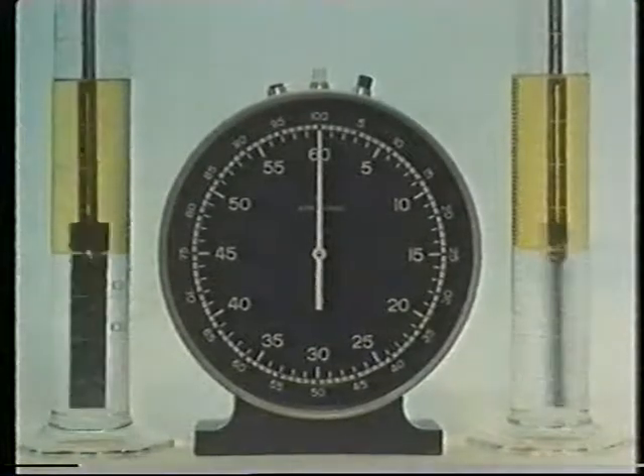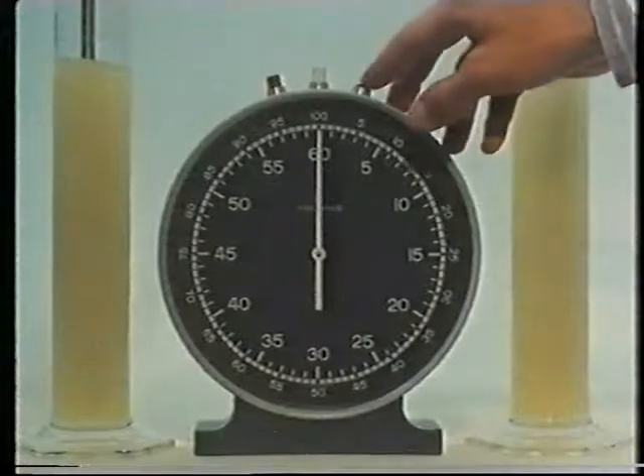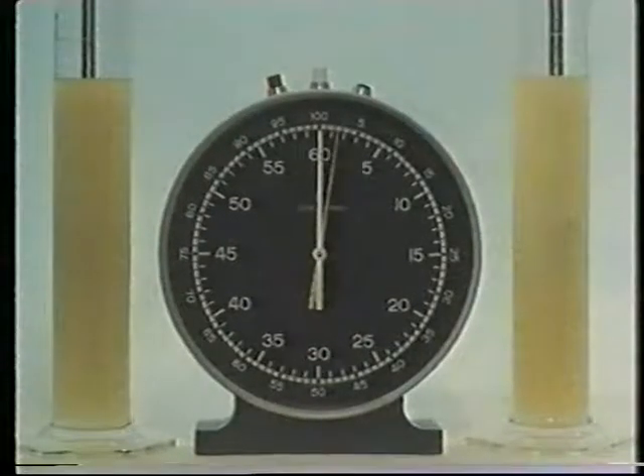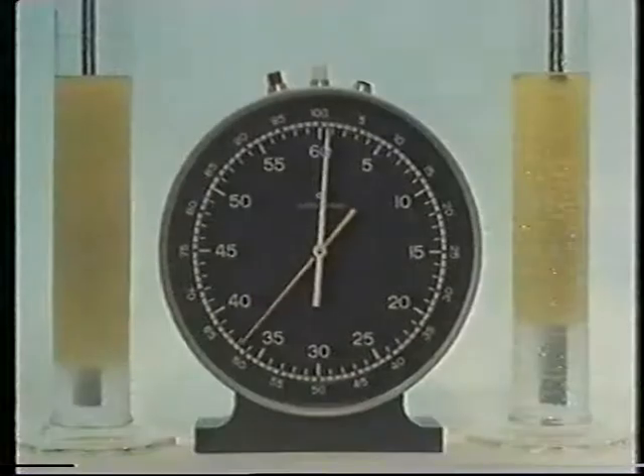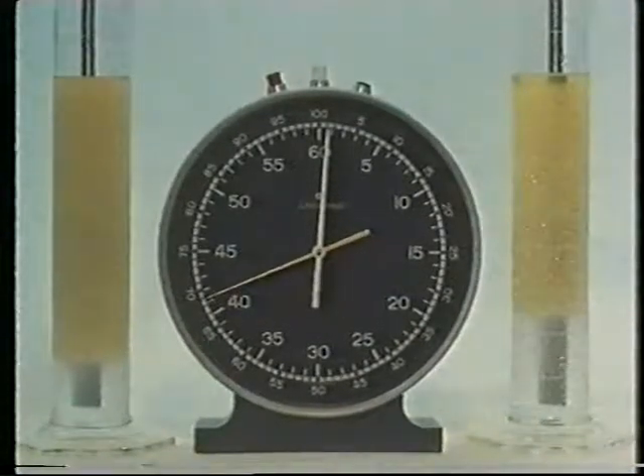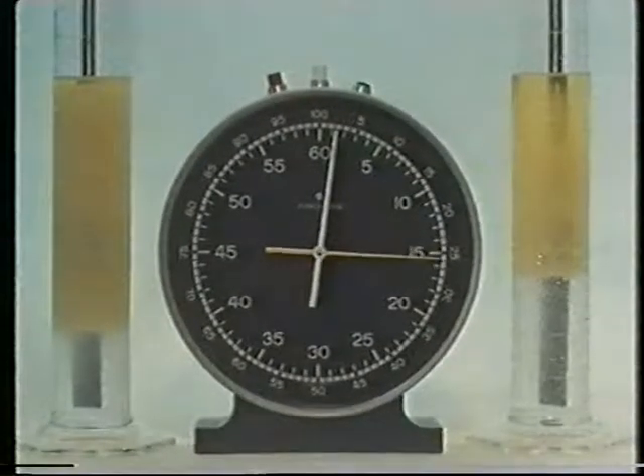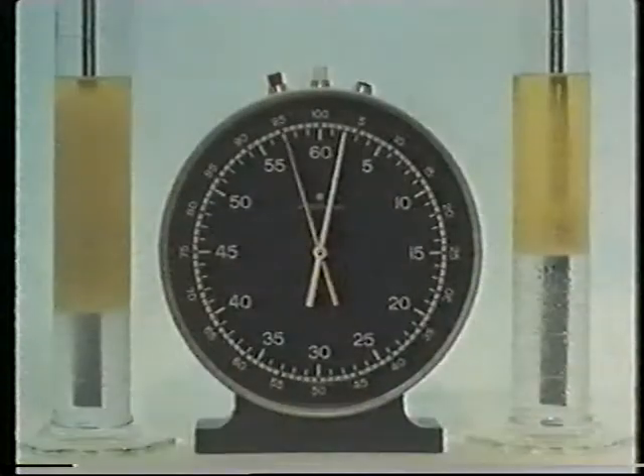Good water separation properties are essential in hydraulic oils. Water in the atmosphere condenses on the walls of supply tanks, and gets into hydraulic systems, where it can cause damage. Here, oil and water are stirred into an emulsion. Well-refined, clean oils demulsify rapidly, and the oil floats to the top. Once separated from the oil, water can easily be drained from the hydraulic system reservoir.